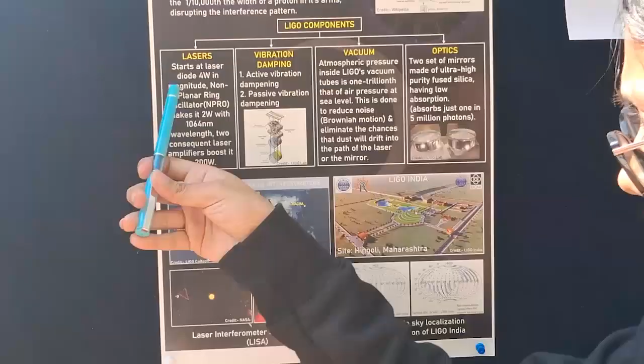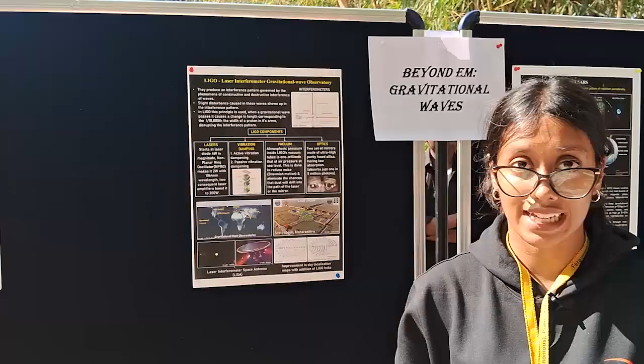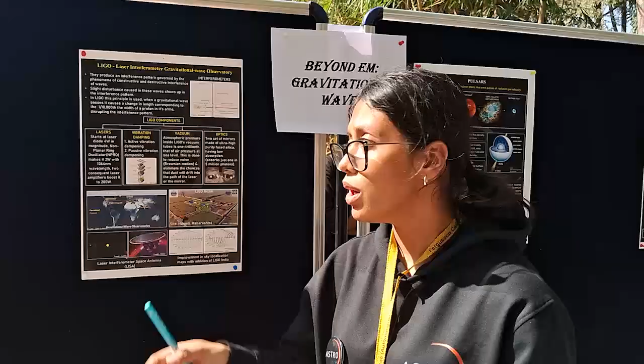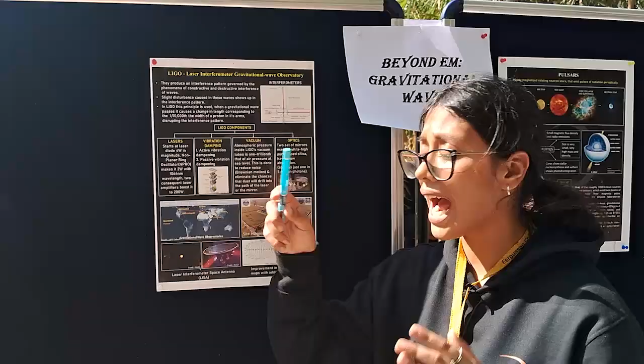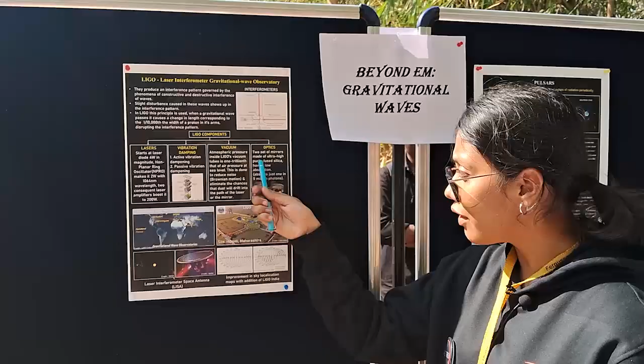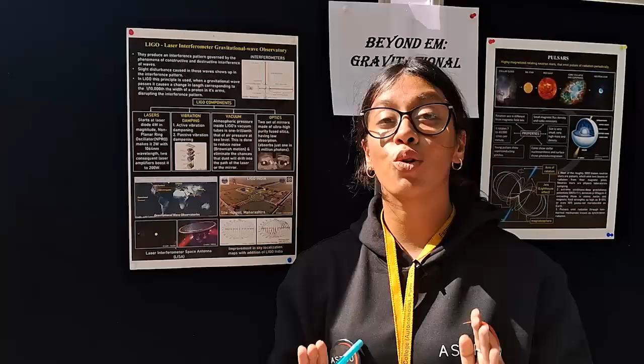The laser, which starts off at 4 watts, eventually becomes 200 watts and it is an infrared laser. Of course, we also have a vibration damping system which is used to eliminate any vibration that may interfere with the light waves. We also have a vacuum which is 1 trillionth the atmospheric pressure at sea level. This is done to reduce Brownian motion and to remove any particles interacting with it. And of course we have mirrors here which are ultra high purity fused silica mirrors which are capable of absorbing only 1 in 5 million photons. So yeah, that was all about LIGO.